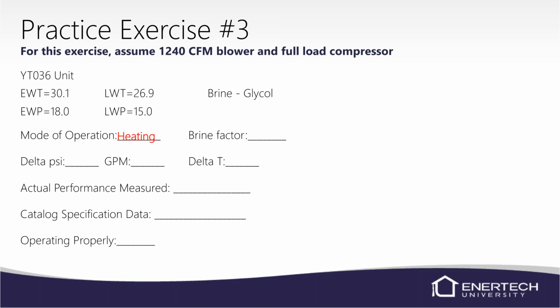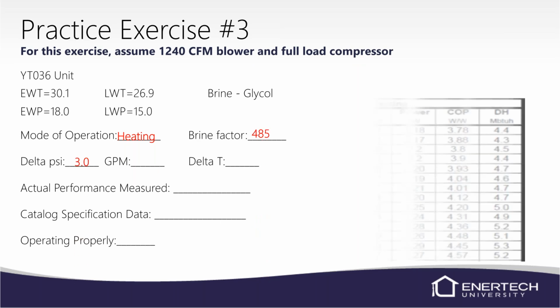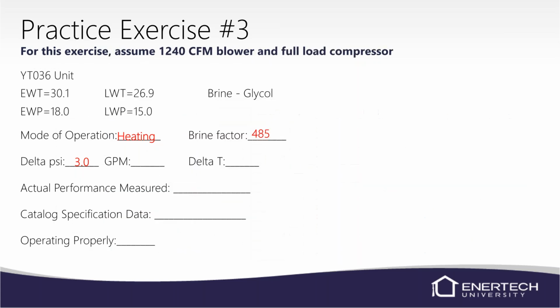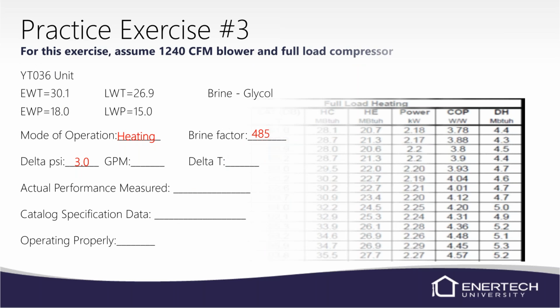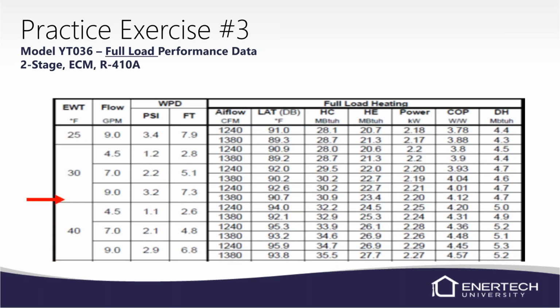So we know our temperature difference. We know we're in heating mode because our entering water temperature is higher than our leaving water temperature. The brine factor for antifreeze, in this case glycol, is going to be 485. So we know our pressure drop was 3. We'll go ahead and pull up that manual again. Let me go back. We had 30-degree entering water temperature and a 3-pound pressure drop. So 3.2 is pretty close. That tells us we're moving the right amount of water flow.